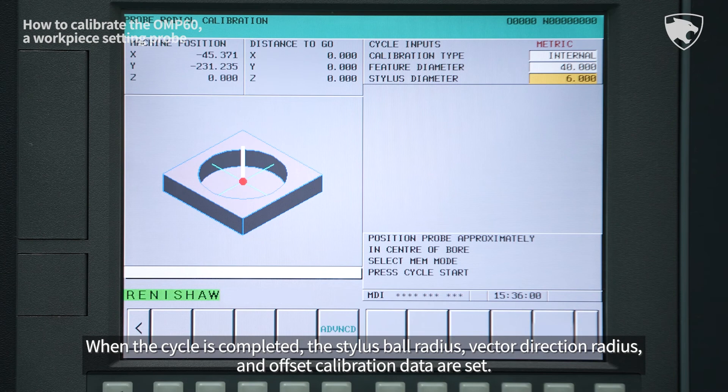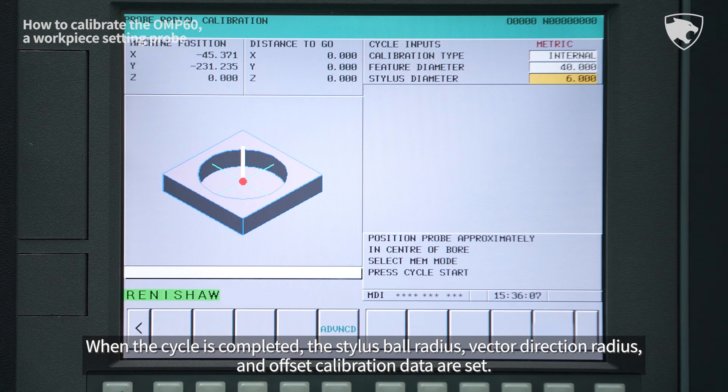When the cycle is completed, the stylus ball radius, vector direction radius, and offset calibration data are set.